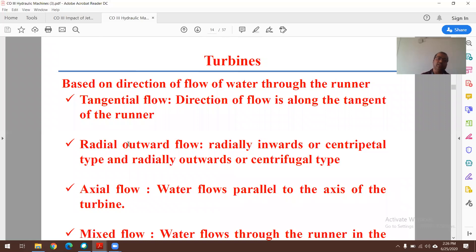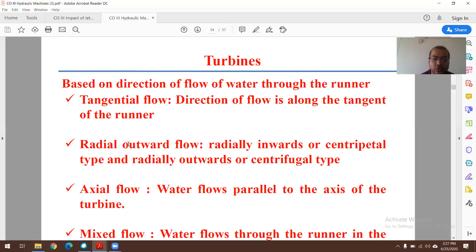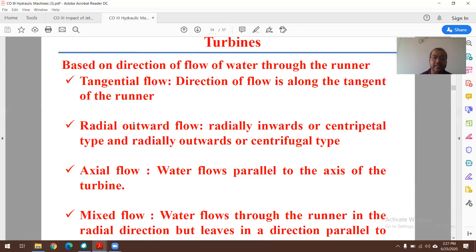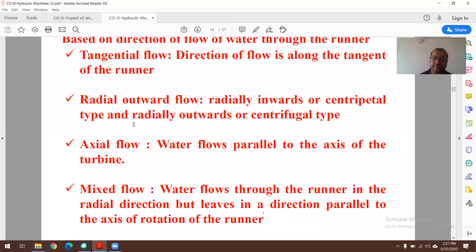Turbines can also be classified based on the direction of flow of water through the runner: tangential, radial, axial, and mixed flow. In tangential flow, the direction of flow is along the tangent of the runner. In radial flow, water flows radially inward (centripetal). In axial flow turbines, water flows parallel to the axis of the turbine. In mixed flow turbines, water flows through the runner in the radial direction but leaves in a direction parallel to the axis of rotation.